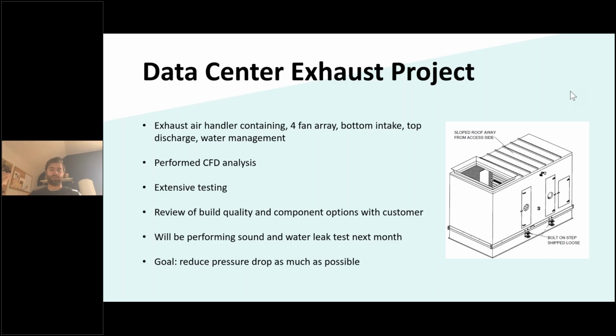So we had a large data center manufacturer approach us looking for a way to exhaust air from their building with noise reduction in comparison to upblast fans. Their facilities were starting to be encroached by neighborhoods, and they wanted to avoid complaints about the noise. So they approached us about this unit. Additionally, it needed water management involved, and our solution here was to have a bottom fed unit, turn the air 90 degrees, and fire it out the top again.